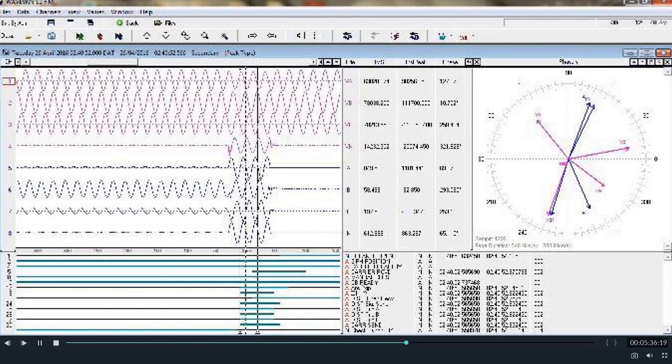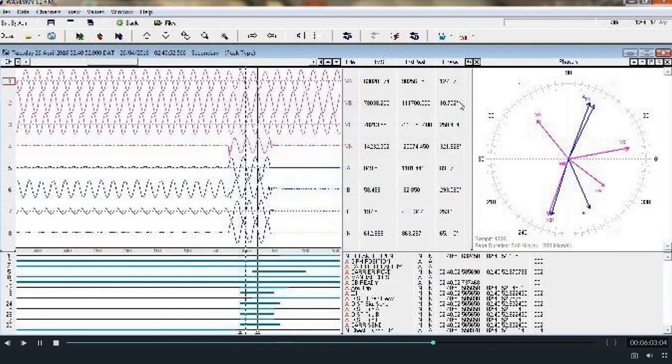At the same time, if you observe the voltage graph, the voltage was reduced during the faulty condition, and when the line was opened by opening the circuit breaker, the voltage of the line was again restored to healthy values. So from this it is understood that the line was opened from this end, and from the remote end the line was not opened. Because of that, due to the opening of the circuit breaker, the current became 0, but the voltage was still there in the line.